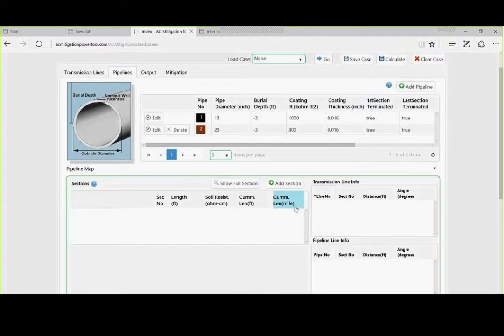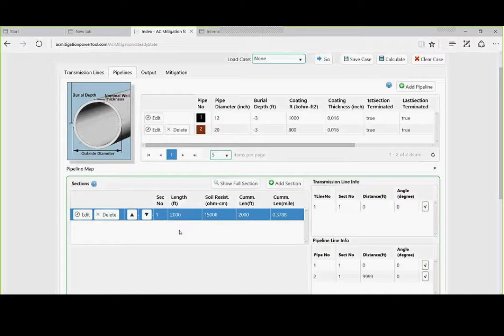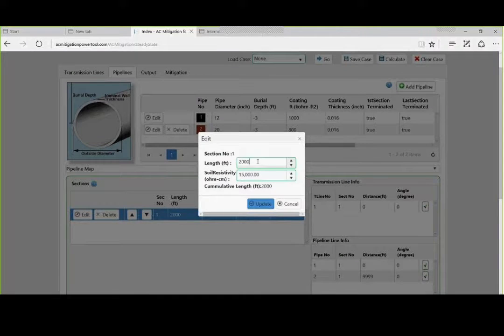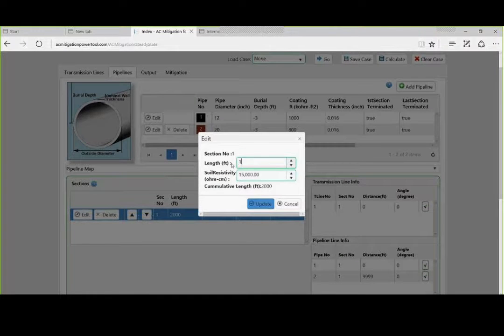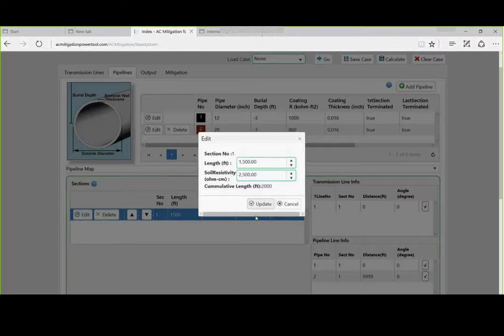Now what is the next thing? We have to add sections. So let's add our first section. And this is the menus down below. We are going to add a section. And you notice it defaults to 2,000 feet, 15,000 ohm centimeter. And here is your cumulative length and here is your cumulative miles. I am going to change this to lengths of 1,500 feet. And we are going to make the soil resistivity. We determined that it was 2,500 ohms all the way. We could change it for every section if we want.